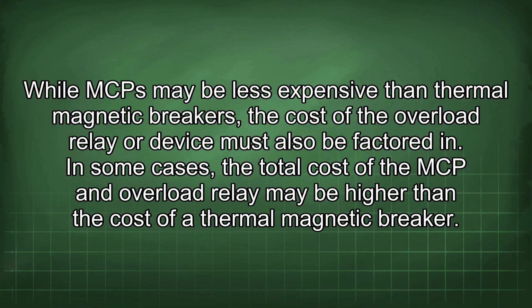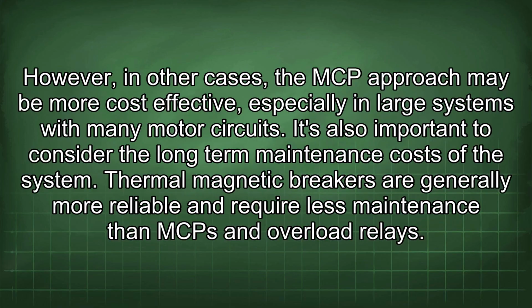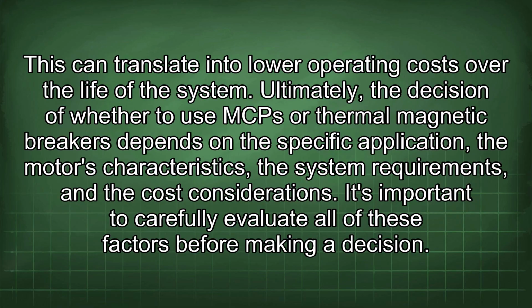In some cases, the total cost of the MCP and overload relay may be higher than the cost of a thermal magnetic breaker. However, in other cases, the MCP approach may be more cost-effective, especially in large systems with many motor circuits. It's also important to consider the long-term maintenance costs of the system. Thermal magnetic breakers are generally more reliable and require less maintenance than MCP and overload relays. This can translate into lower operating costs over the life of the system.